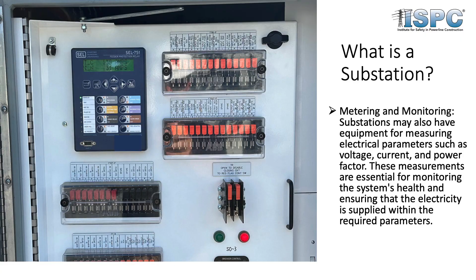So the last thing that we'll talk about inside, or what is a sub, is metering and monitoring, right? So not only does equipment like circuit breakers open and trip for faults and things of that nature, but those are monitored by metering and relaying, okay? So we're looking at currents, we're looking at faults, right? Ground, phase to ground, phase to phase. We're looking at things like power factor and stuff like that, bus voltages, line current, things of that nature. And these relays monitor the health of our system, right? So again, they will tell this equipment when to isolate a fault, when to trip.